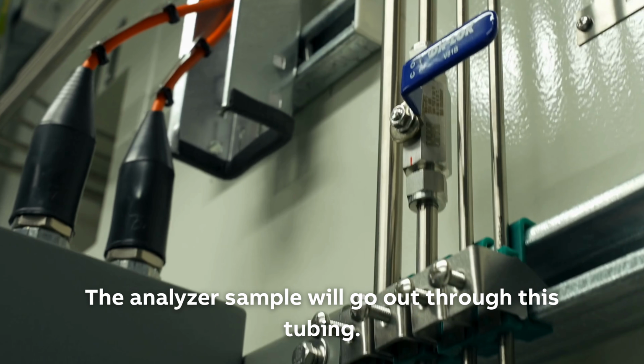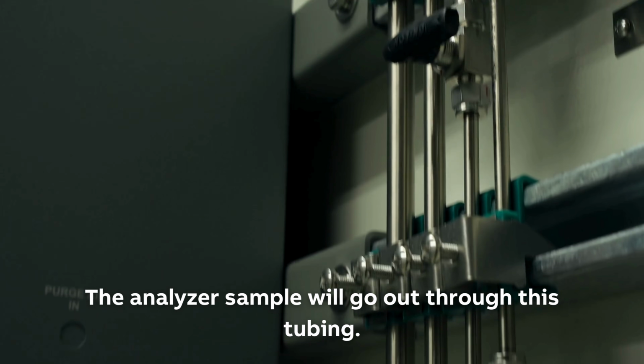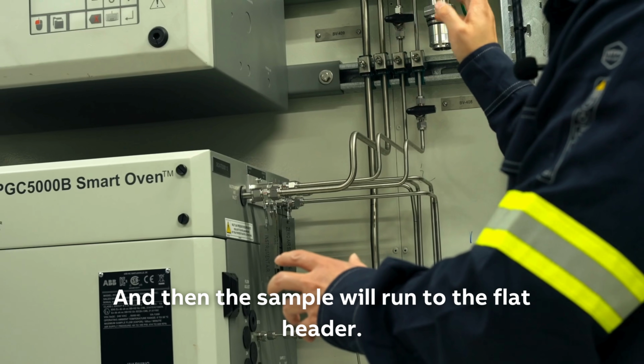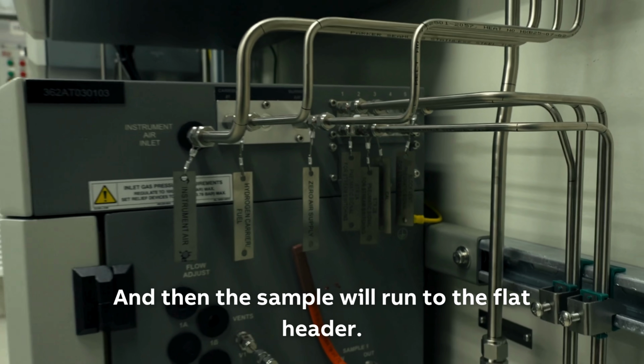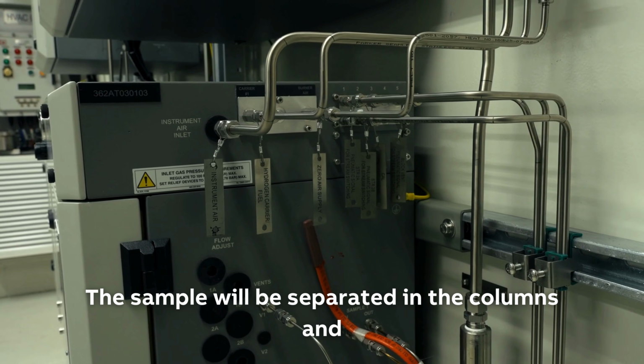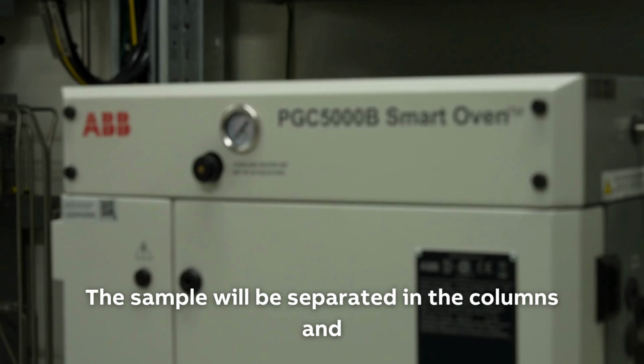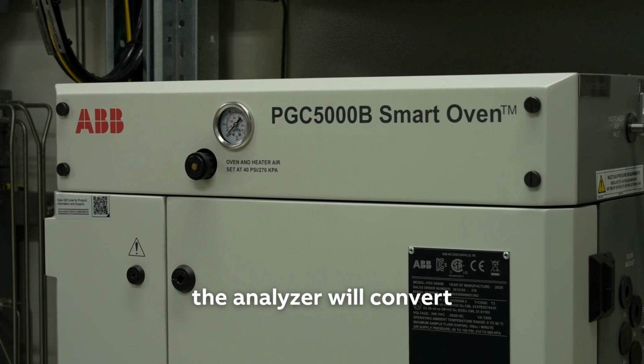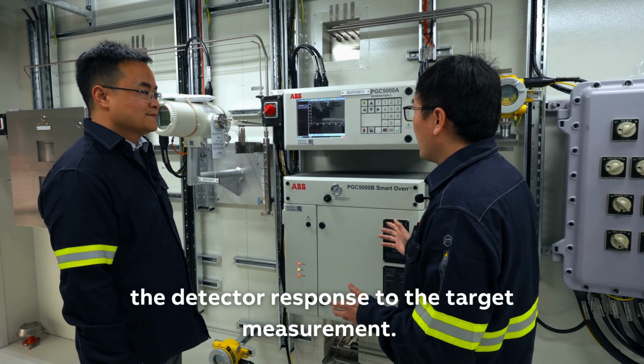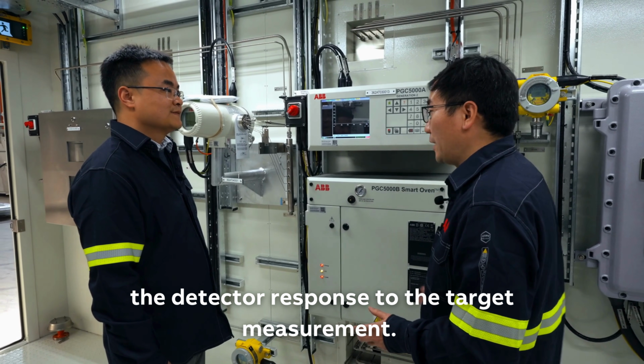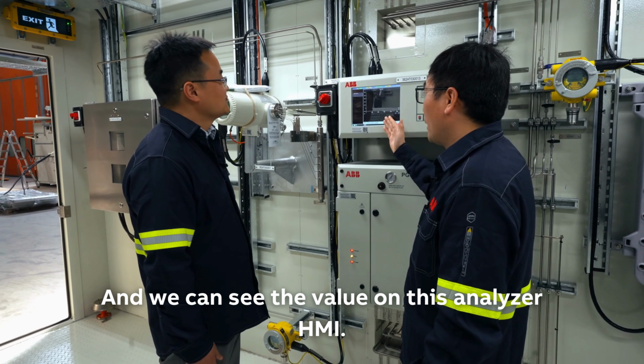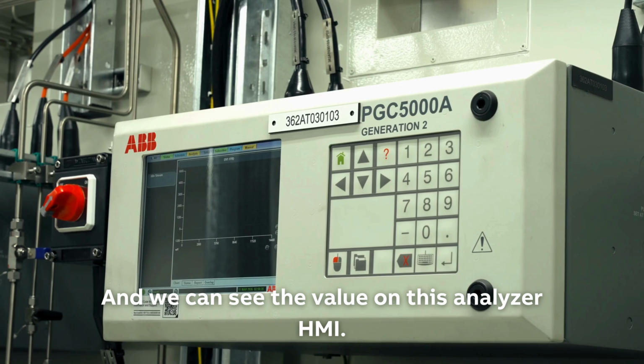The analyzer sample will go out through this tubing, and then the sample will go to the flat header. The sample will be separated in the columns, and the analyzer will convert the detector response to the target measurement values. And we can see the value on this analyzer HMI.